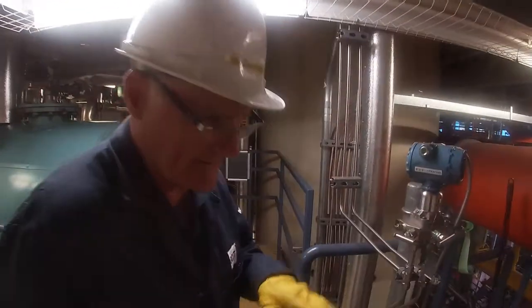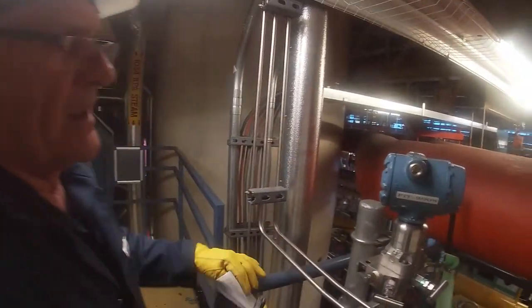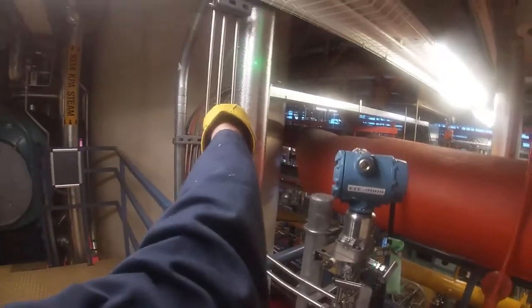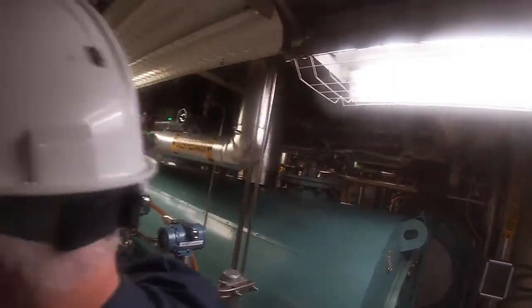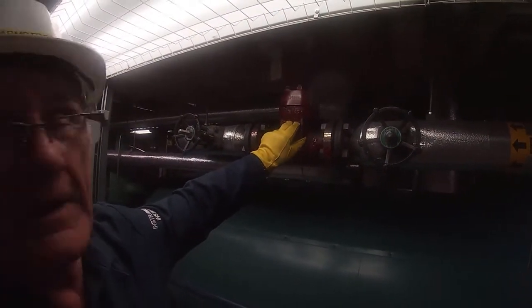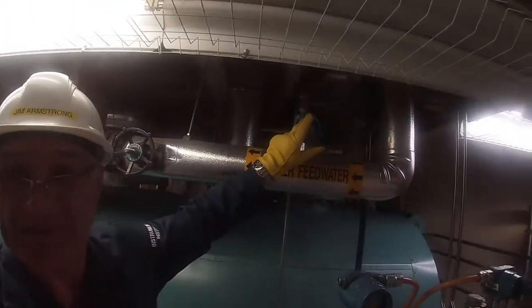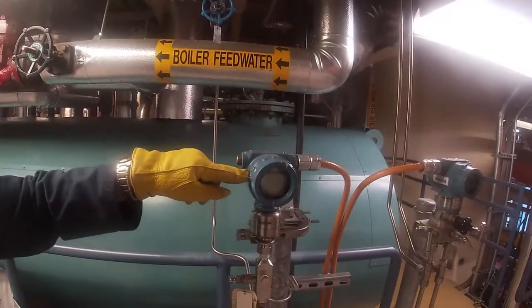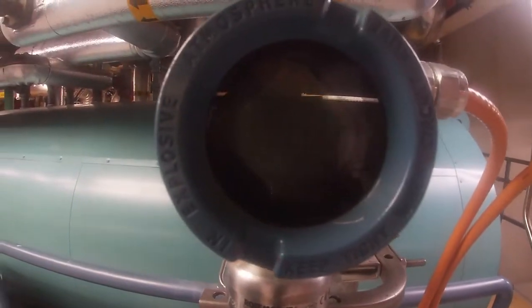Okay, we're back upstairs because the feed water line came up. This is the feed water line right here. The feed water comes up on this line. If I could just back up a little bit, right there is a T. Through that line, it comes down and goes through this Masoneilan Linc-lock valve, and that valve is controlling the pressure. In fact, the pressure is being sensed right here. There's the pressure transmitter, and I don't know whether you can see it. Right now, it's running at 2,070 kilopascals, which is typically what we're trying to run at.